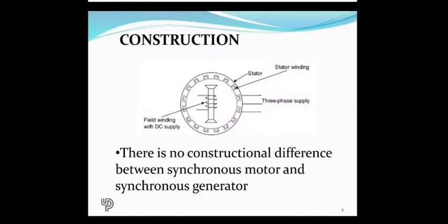The synchronous flux is rotating at a very fast speed. So by the time the rotor starts moving in one direction, the polarity of the stator flux changes in the opposite direction. The rotor tries to move in the opposite direction, and by the time that happens, the polarity again changes for the stator flux and so on. So the rotor essentially tries to start but cannot. You need to give it an initial start, and then it definitely starts and catches up with the synchronous speed of the flux produced in the stator.